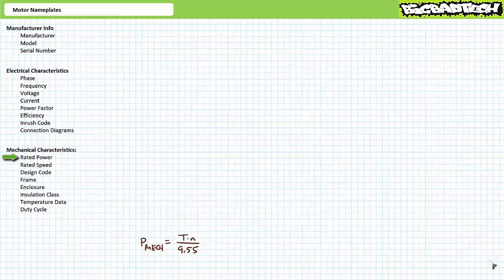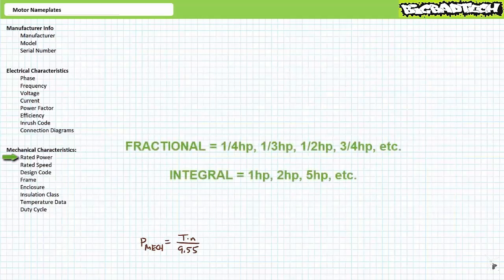As we learned in the mechanical power lecture, available at the Big Bad Tech channel, rotating mechanical power is the product of twisting force called torque in units of Newton meters times rotational speed N in units of RPM divided by the constant 9.55. Motors can be sized in one of 2 general classes, fractional and integral. Fractional motors are those motors less than 1 horsepower, like a 1/4 horsepower, a 1/3 horsepower, or a 1/2 horsepower, i.e. fractions of a horsepower. Integral motors, in contrast, are motors greater than 1 horsepower, like 1 horsepower, 2 horsepower, 5 horsepower, etc.